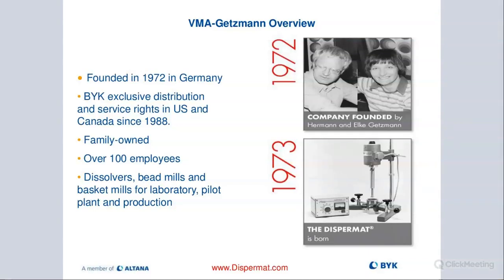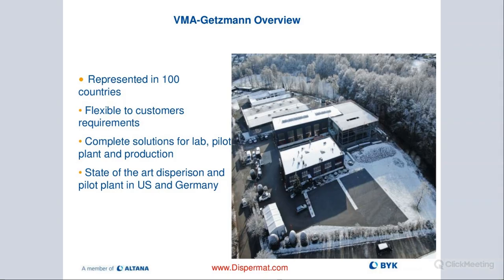It's a small laboratory scale unit. It's called the LC, and we have actually some customers that are still using the original designed Dispermat. So there's unbelievable motor technology, but they only replaced the control panel, or the little control unit, you can see on the left side of the unit. But these motors are brushless step motors. So the shaft actually goes right into the motor. There are no belts or anything of that nature that require maintenance. So these are brushless step motors, extremely quiet and have hardly any vibration.